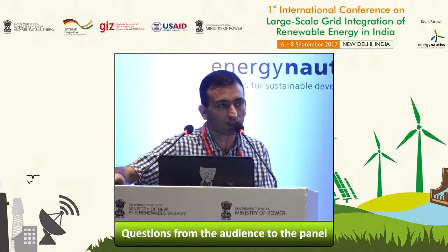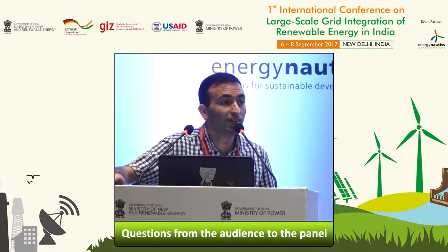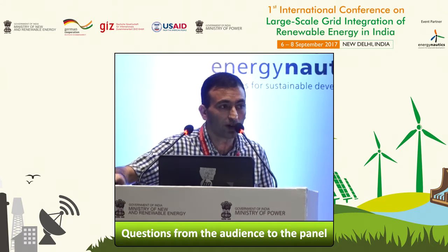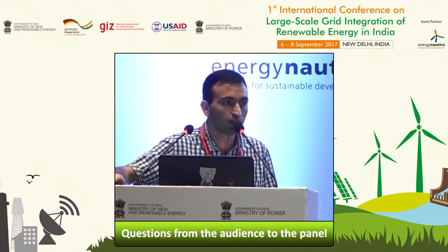But in some particular cases, which I try to highlight here, it so happens that in active power based LVRT, we are going to have less active power injection into the grid compared to the reactive power priority based LVRT. So what that will actually result in aggregate, if we have higher penetration, is a significant shortfall of active power generation, and it may impact the frequency of the grid.